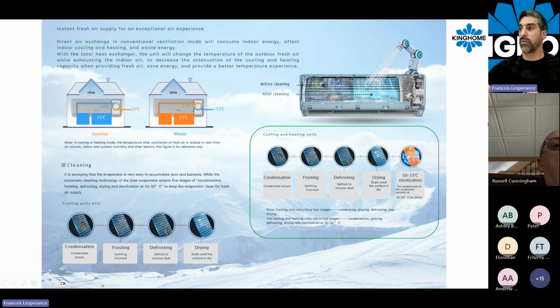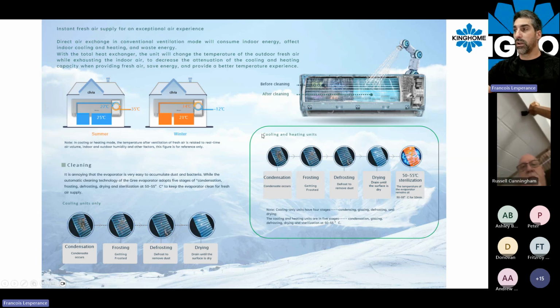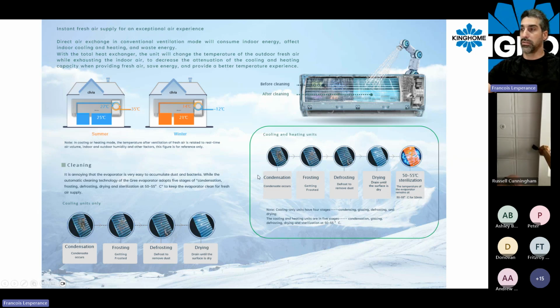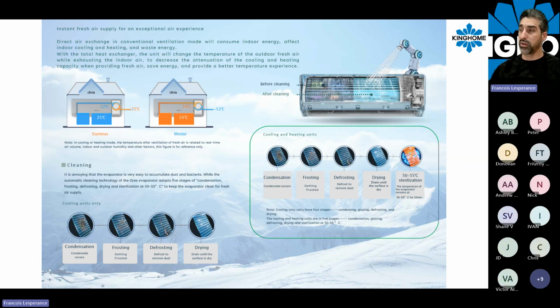So let's focus here on the heat pump system, cooling and heating unit. We will have 5 steps to achieve this cleaning session. The first step is to humidify the coil. The system will go in cooling mode or in dehumidifier mode to bring the coil to have a lot of condensation on it. Then the second step will be to freeze that water.